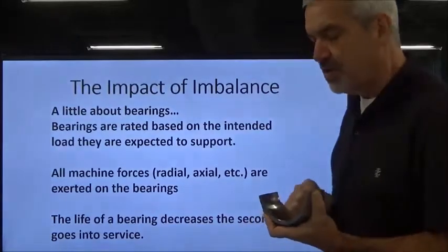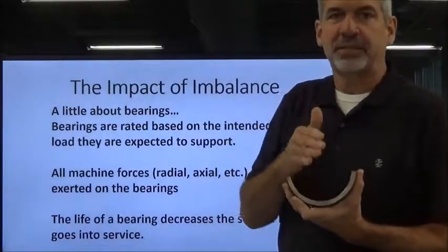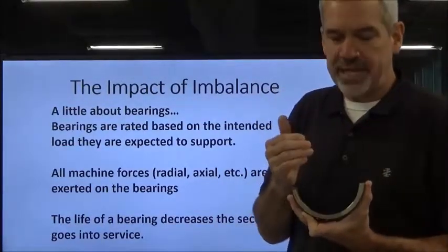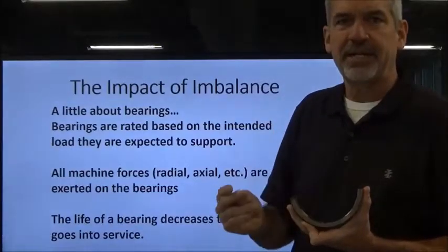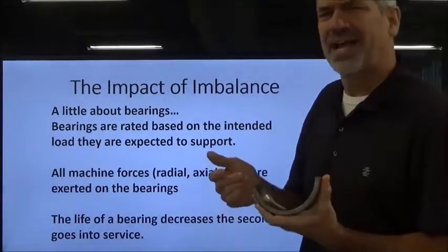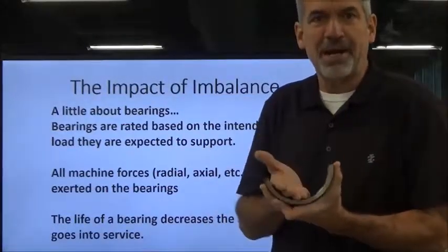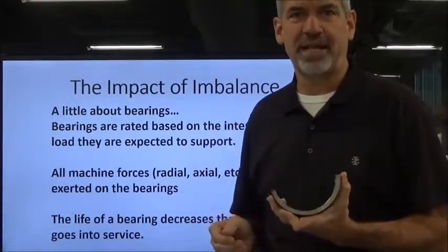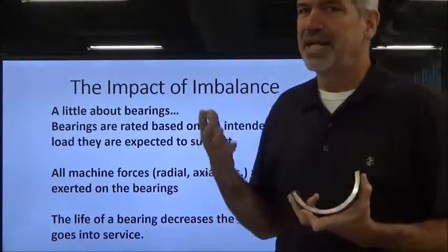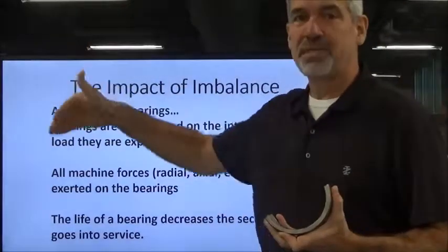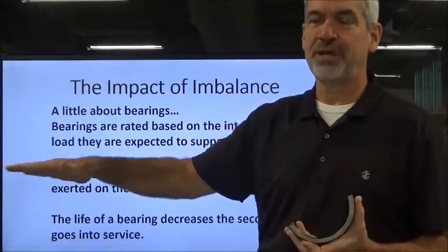Okay, so I put my equipment on there, and I started pulling the data off of it, and immediately it showed it was a bad bearing. I was like, how can that be? Did we change the wrong bearing? What happened? Because it's a brand new bearing, and it was showing defective right out of the gate. Now, it's kind of hard to believe, but data is what it is.